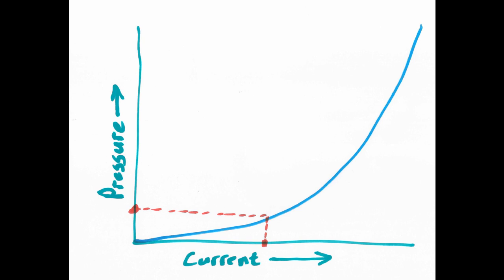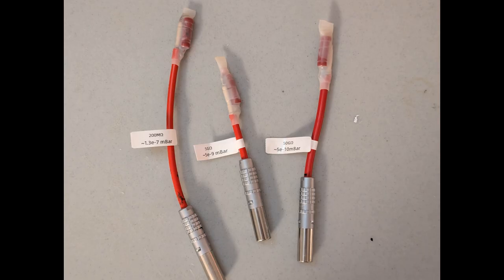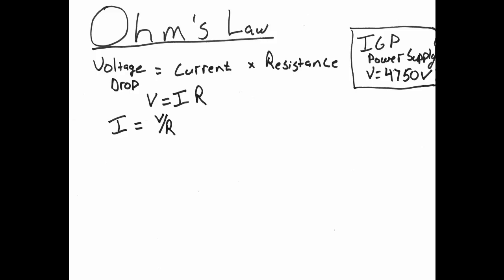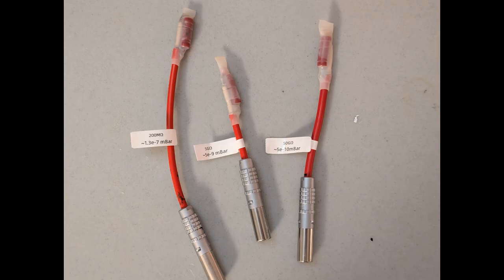Sometimes during maintenance, we're not sure what's wrong. Maybe the power supply is acting up, maybe the pump has failed, or maybe there's a real vacuum issue like a leak. To figure that out, we can swap in a known resistor called a dummy load where the ion pump would normally connect. Because we know the voltage and the resistance, we can calculate the current using Ohm's law. That results in a fixed pressure reading from the software, or it should. If the pressure looks good with the dummy load, then the power supply is probably fine. We know the issue lies either with the pump, the cable, or maybe even a vacuum leak. This is a consistent way to measure systems and isolate problems.